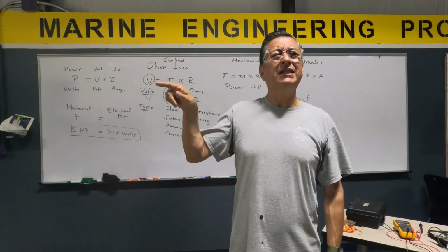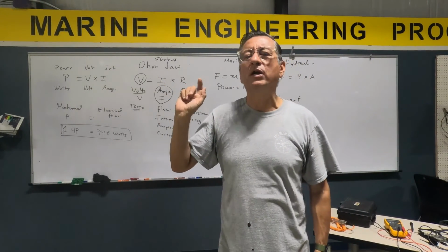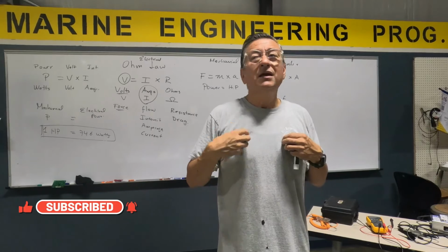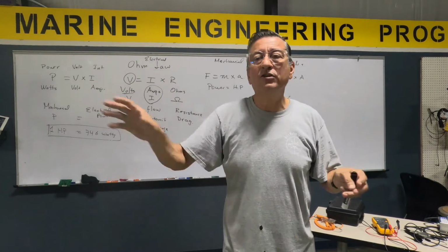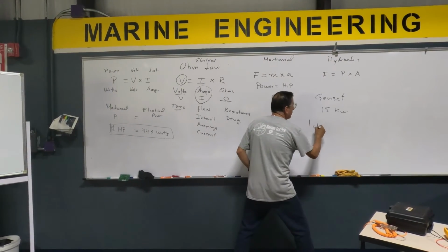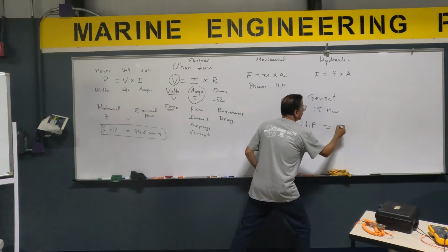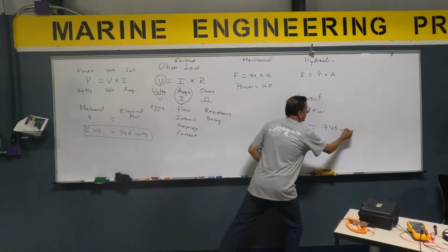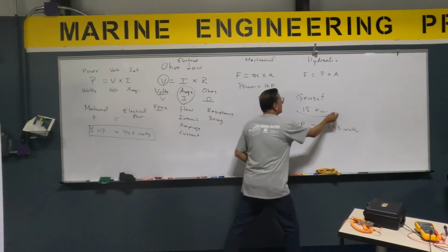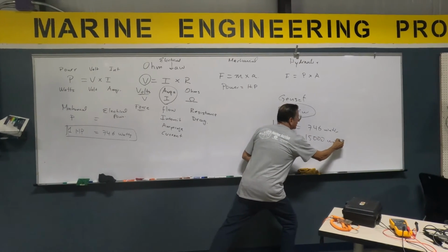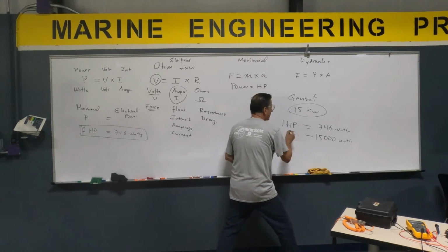How much should be the power of the engine in horsepower? You understand? I need to replace that engine for another engine in the market. But the question is, what is the horsepower of the new engine appropriate for that generator? 20 horsepower? I say that 1 horsepower is equivalent to 746 watts. Actually, my generator has 15,000 watts.